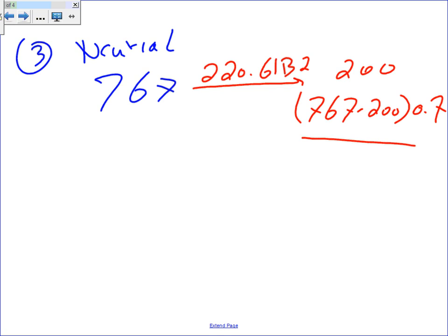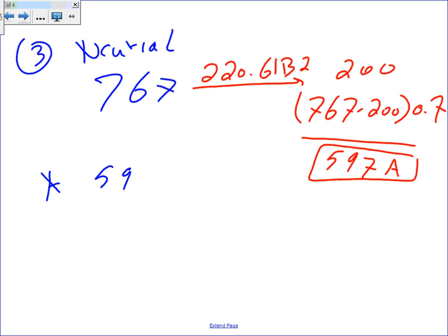So from 220.61(B)(2), don't forget to add the first 200. 597. Any second? Okay, all right, so then here's my amps. I have 597. Since I paralleled the hots, is it wrong, Chris? Did you come with something different? Did they get a second? They have two sets, right? Okay, so divide by two.